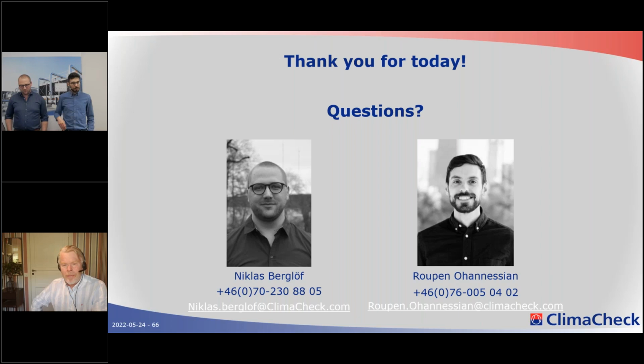Yeah, I think I can answer. So yes, if you have bad performance of the condenser or the evaporator, there can be different reasons which cause it. And you should be able to check with other KPIs. Let's say you have a high condensing temperature, and that might be because your condenser is dirty and needs to be cleaned, or the fans are not running. If you're measuring the fan power as well, you would be able to notice that the fan power is not really as it should be.